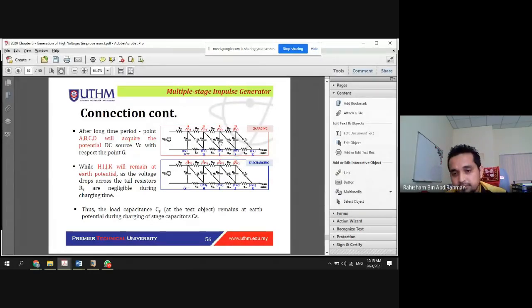Hence the total voltage level at a particular value will be far lower than the desired value. So once we expect the voltage to be 400 kV, we might end up with about 350 kV because they are not discharged at the same time. It's very hard to control. Even when we put the trigger, spark gap 1 may trigger maybe 10 milliseconds faster than the other one.